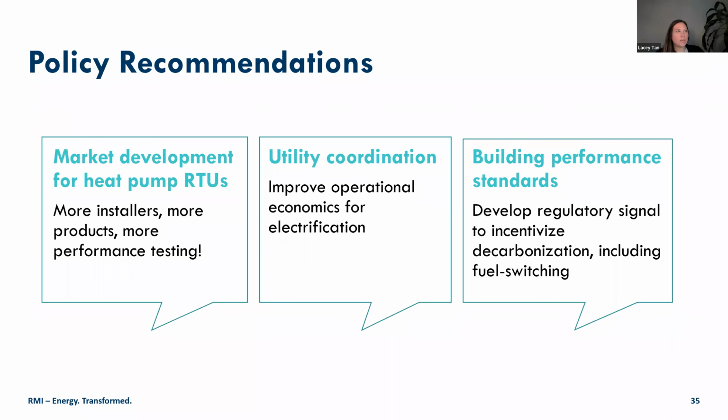Do you think, Anish, that would be more applicable to new commercial buildings, or do we think that could work in existing? I think it could work in existing to make the economics look better, acknowledging that it might be a very valuable solution in an existing building because it could prevent you from having to upgrade your electrical panel or electrical transformer and capacity of the site. If that's a limitation, peak demand management and batteries are a way to mitigate that. So it could actually bring your first cost down. So, yeah.